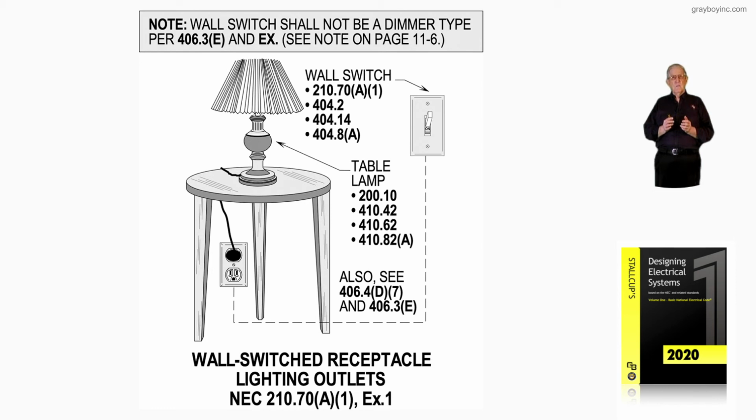404.2 deals with switches. 404.14 is the loading of switches. And 404.8(A) deals with the handle and the on position of that switch should be no higher than 6 foot 7 inches.